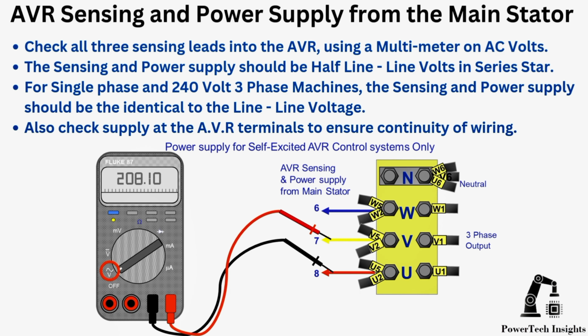AVR sensing and power supply from the main stator. Check all 3 sensing leads into the AVR using a multimeter on AC volts. The sensing and power supply should be half-line, line volts in series star, for single-phase and 240-volt 3-phase machines. The sensing and power supply should be identical to the line voltage. Also check supply at the AVR terminals to ensure continuity of wiring.